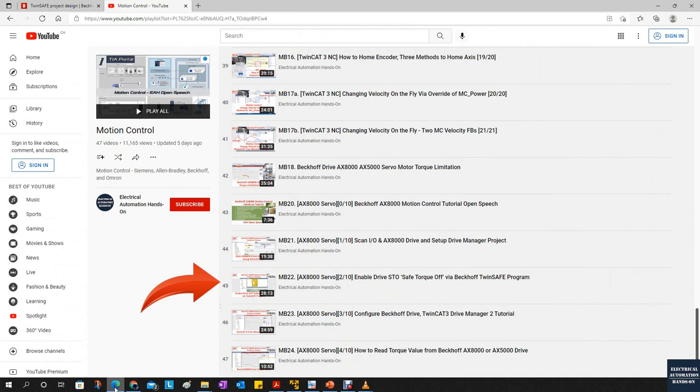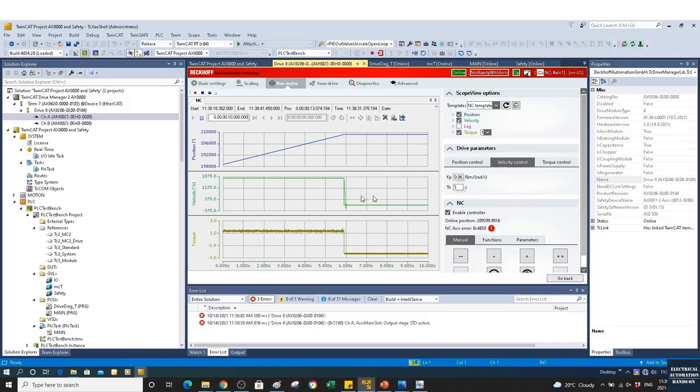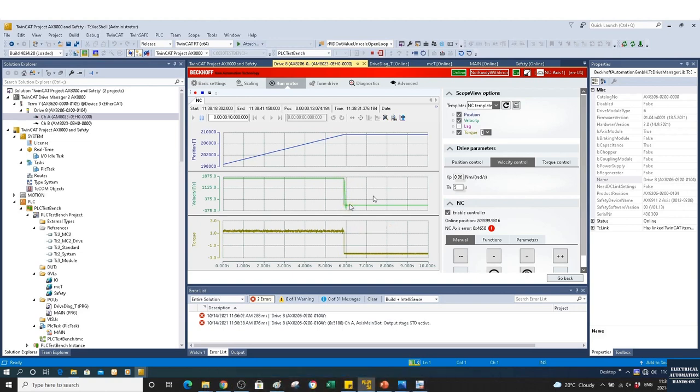SS1 and STO — if you recall from the number two video, we discussed how to implement the STO Safe Torque Off function. The difference between STO and SS1: with STO, when you hit the e-stop or the STO signal is de-energized, the drive will lose torque and you will see the drive run down by itself, because the torque is totally off but the mechanical system still has inertia, so the drive will still travel a very short distance and free-run down.